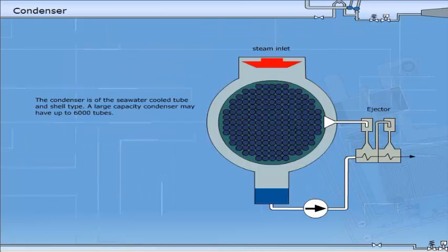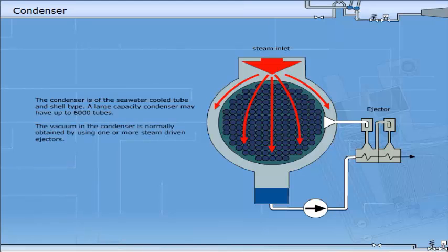The condenser is of a seawater-cooled tube and shell type. A large-capacity condenser may have up to 6,000 tubes. The vacuum in the condenser is normally obtained by using one or more steam-driven ejectors. By lowering the vacuum, one may pull more power out of the turbine. But on the other hand, the temperature of the condensate will also be lower, and the total plant efficiency will be reduced.